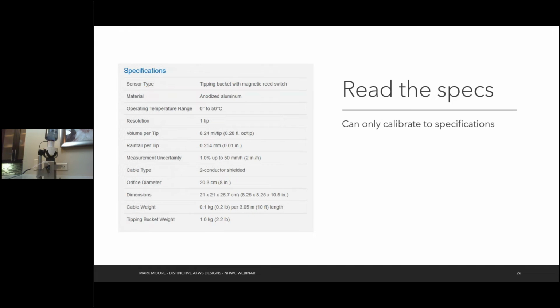So this is a screenshot from a tipping bucket calibration spec sheet. And you can see that the measurement uncertainty is 1.0% up to 2 inches an hour. So it should be accurate to 1% error, but that's only assuming it's raining less than 2 inches an hour. That might be a little hard for people to conceptualize, so let me give an example. 2 inches an hour is about when you're on the highway and you're getting a little nervous, thinking, man, it's raining so hard, maybe it's about time I pull off the highway. Places like Gulf Coast regions can easily see 4, 5, 6 times 2 inches an hour. But the idea is that 2 inches an hour is a pretty significant rainfall rate. And if you're getting that much rain, it's pretty heavy. And this example specification sheet says that it's 1% accurate up to 2 inches in an hour.